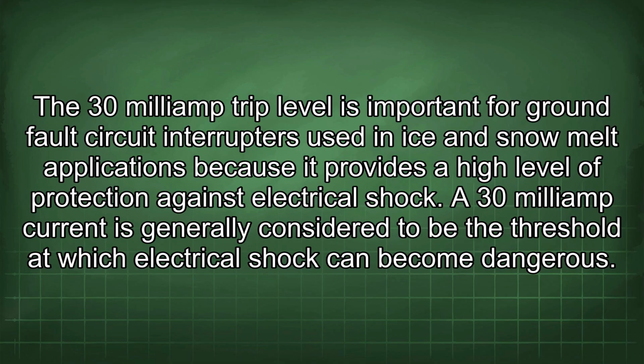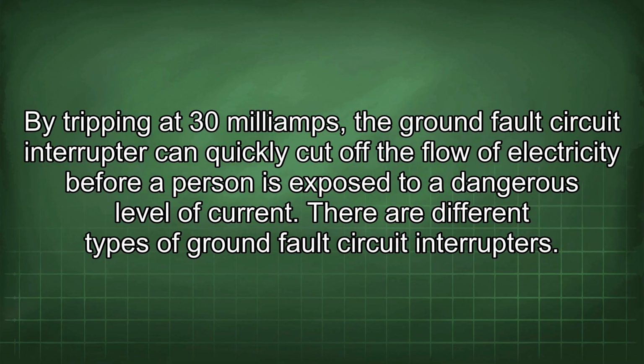The 30 mA trip level is important for ground fault circuit interrupters used in ice and snow melt applications because it provides a high level of protection against electrical shock. A 30 mA current is generally considered to be the threshold at which electrical shock can become dangerous. By tripping at 30 mA, the ground fault circuit interrupter can quickly cut off the flow of electricity before a person is exposed to a dangerous level of current.